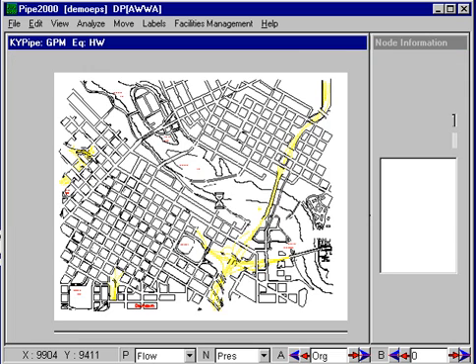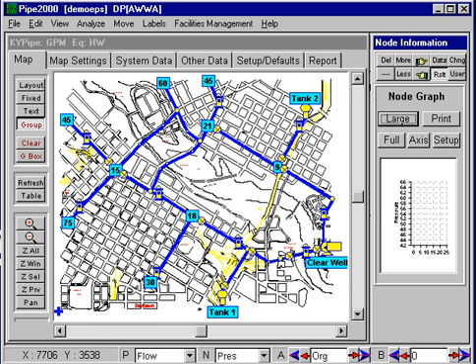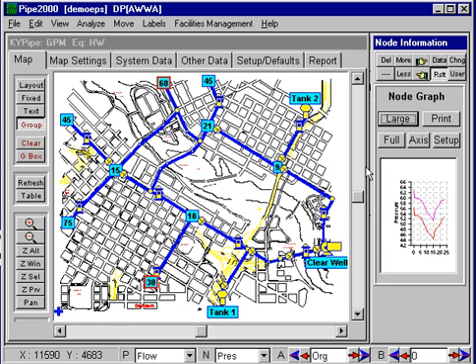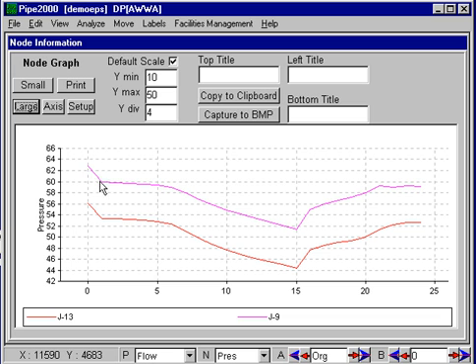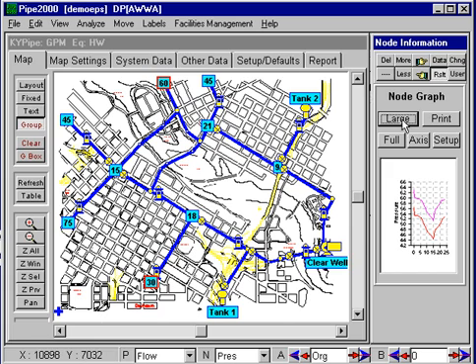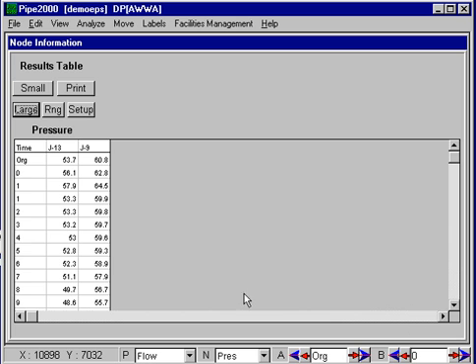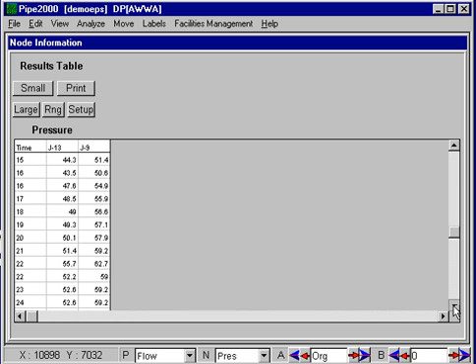One of the better ways to look at the results is through plots and tables. We can select a node and see a plot of pressure versus time. In group mode, we can select several nodes and look at pressure at these points — going above 60, down below 50 — during the peak demand period. We also have tables where we can select any number of nodes and scroll through to see the maximum and minimum pressures.